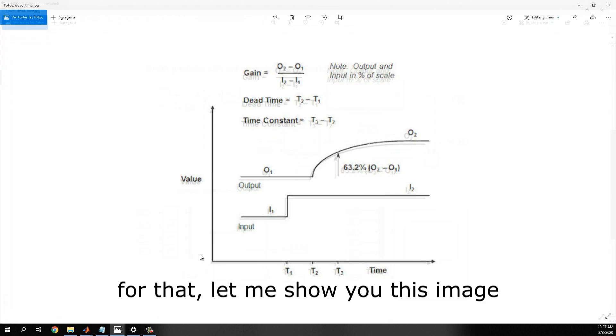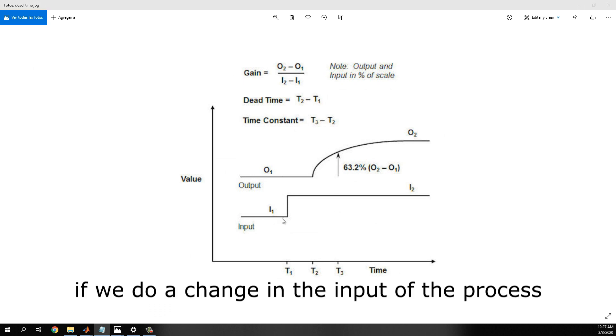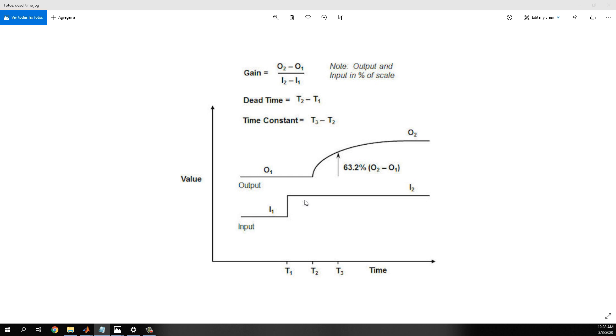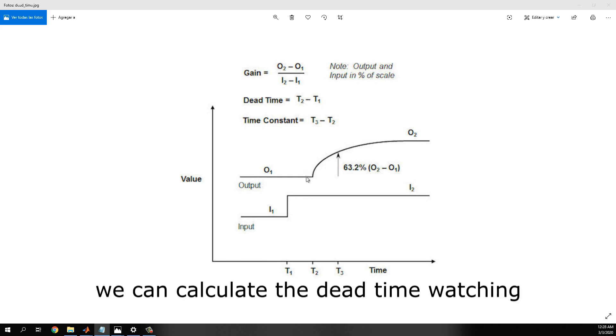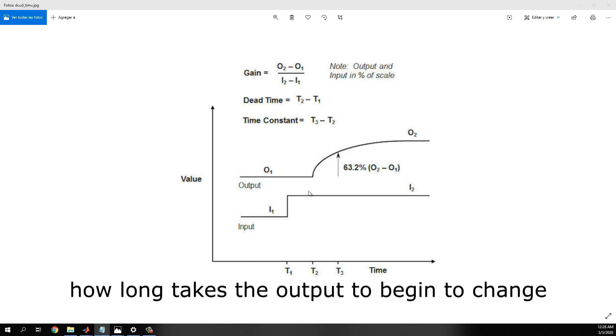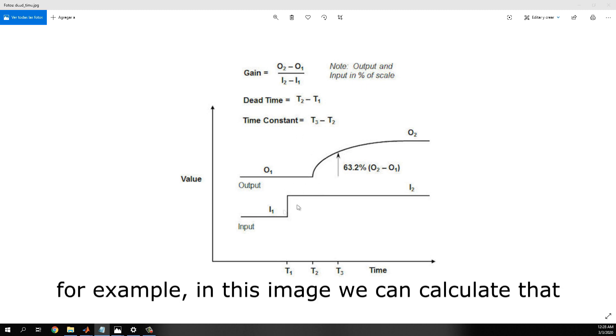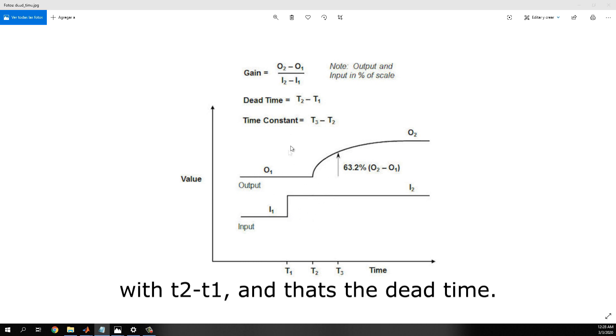For that, let me show you this image. If we do a change in the input of the process, we can calculate the dead time watching how long it takes the output to begin to change. For example, in this image, we can calculate that with T2 minus T1, and that is the dead time.